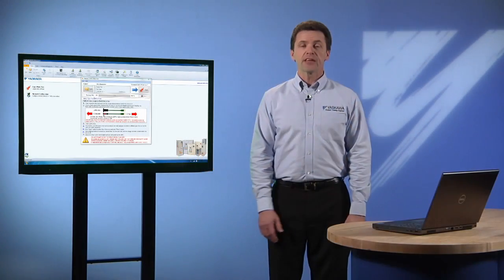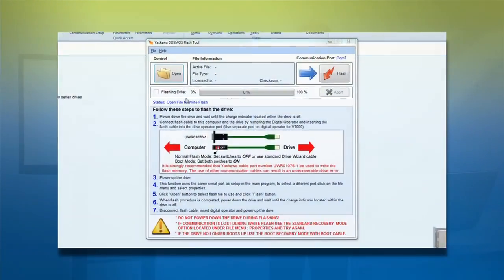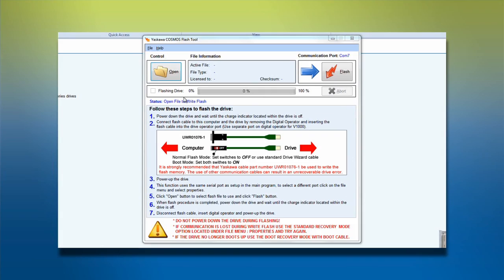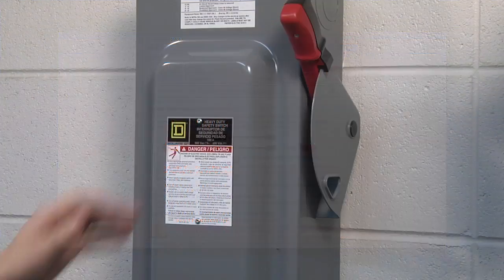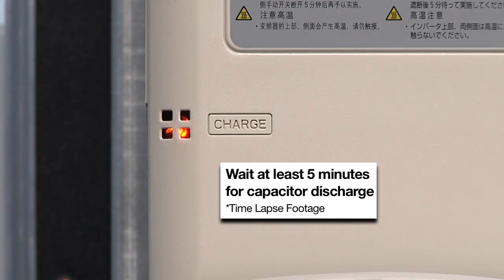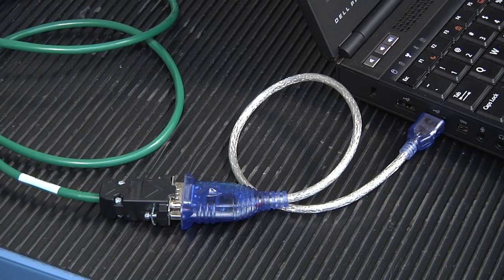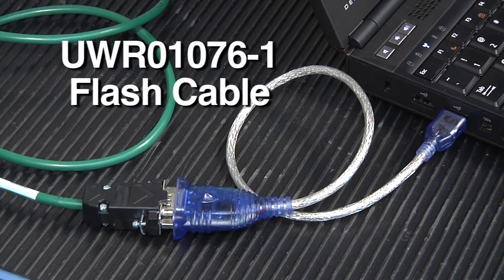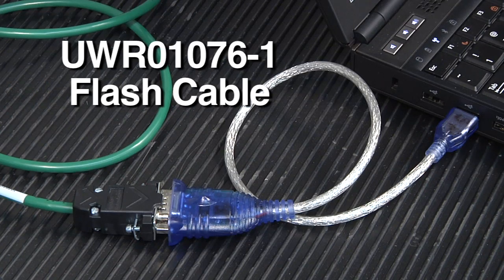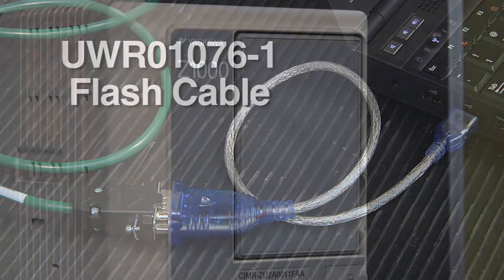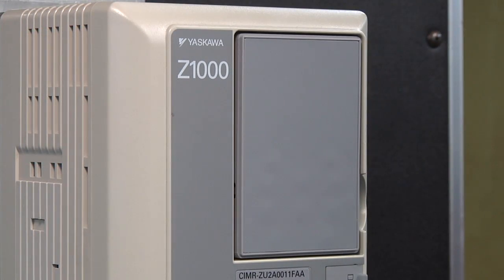From this point, flashing the drive and the bypass is a simple matter of following the steps on the Flash Tool screen. Begin by powering down the drive and waiting until the charge indicator is off. Connect the boot flash cable to the computer. Yaskawa recommends using a UWR01076-1 flash cable.